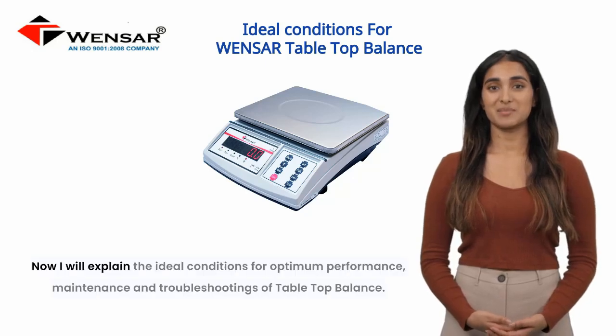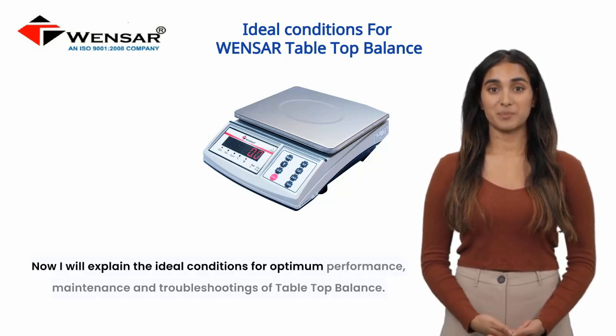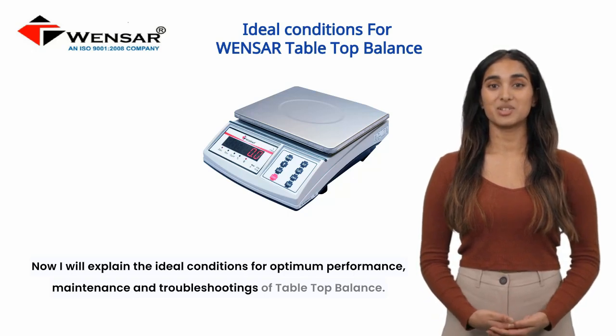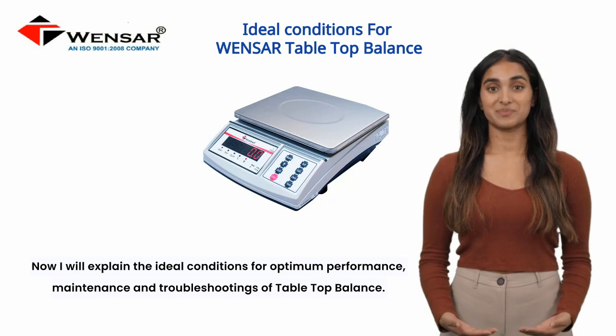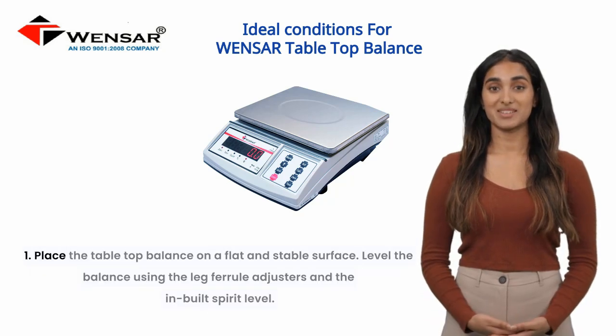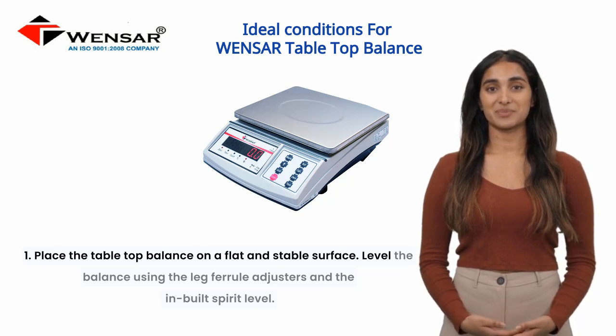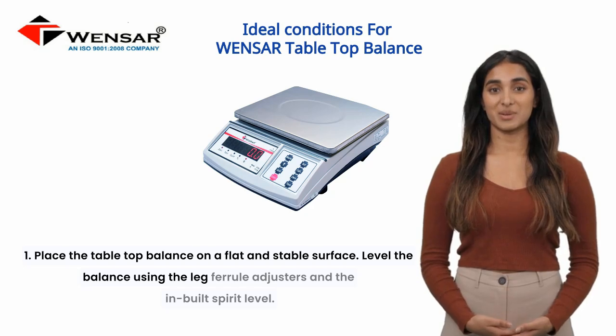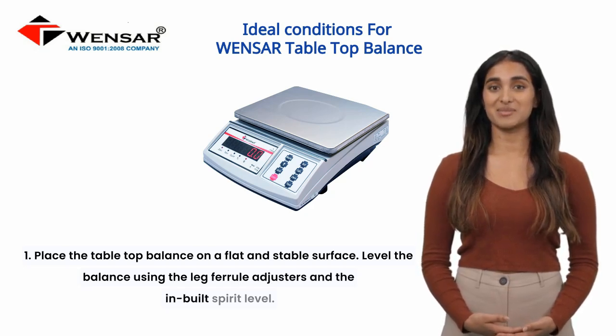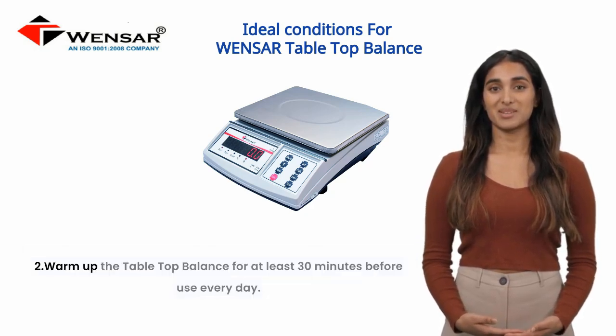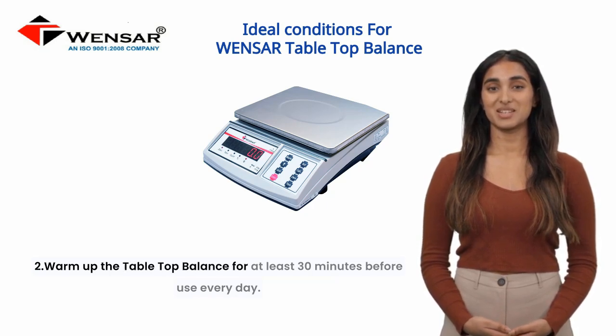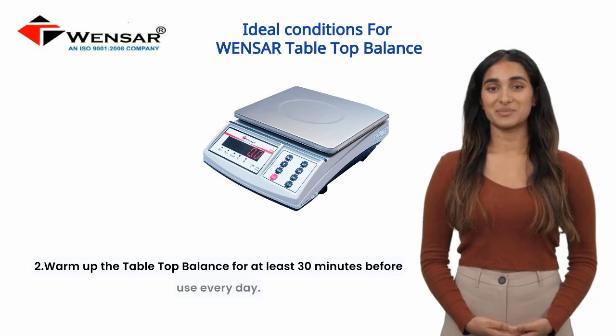Now, I will explain the ideal conditions for optimum performance, maintenance, and troubleshooting of tabletop balance. 1. Place the tabletop balance on a flat and stable surface. Level the balance using the leg ferrule adjusters and the inbuilt spirit level. 2. Warm up the tabletop balance for at least 30 minutes before use every day.